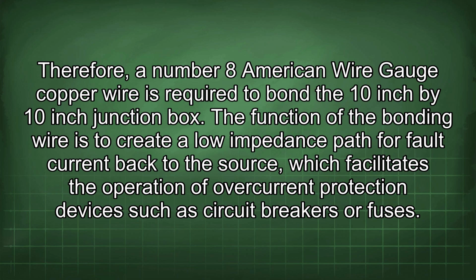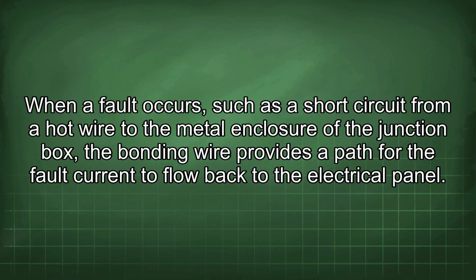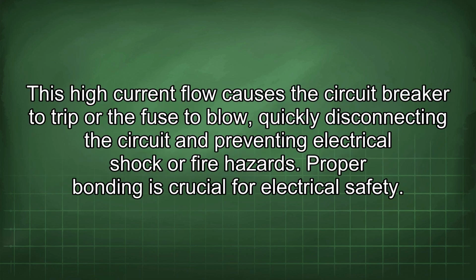The function of the bonding wire is to create a low impedance path for fault current back to the source, which facilitates the operation of overcurrent protection devices such as circuit breakers or fuses. When a fault occurs, such as a short circuit from a hot wire to a metal enclosure of the junction box, the bonding wire provides a path for the fault current to flow back to the electrical panel. This high current flow causes the circuit breaker to trip or the fuse to blow, quickly disconnecting the circuit and preventing electrical shock or fire hazards. Proper bonding is crucial for electrical safety.